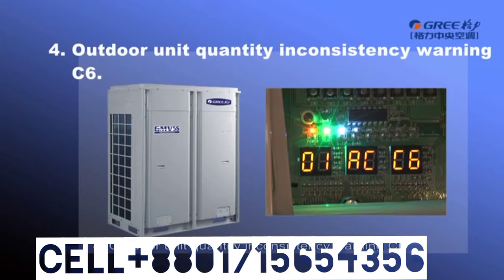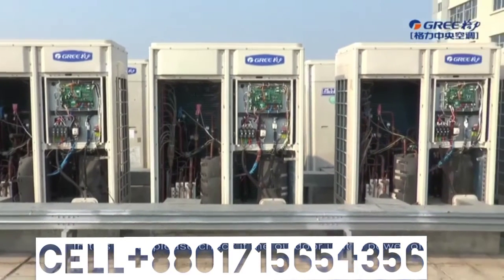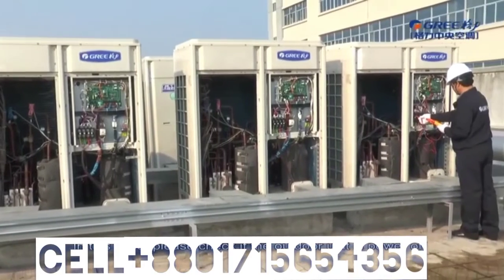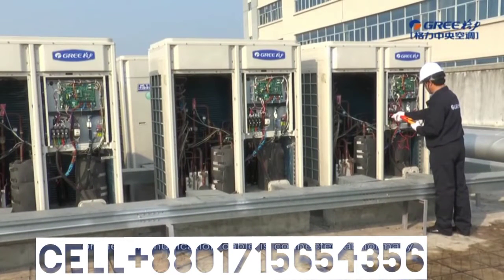Four. Outdoor unit quantity inconsistency warning, C6. When C6 appears, it means the current online module quantity is less than the quantity confirmed in debugging. The system is not allowed to operate. In this case, please check if the outdoor unit is powered off or the communication cable is connected abnormally.